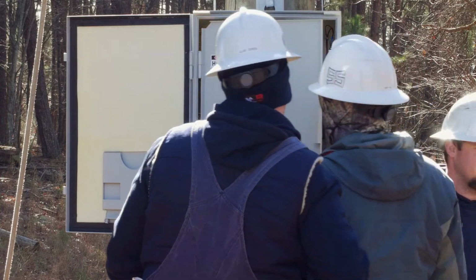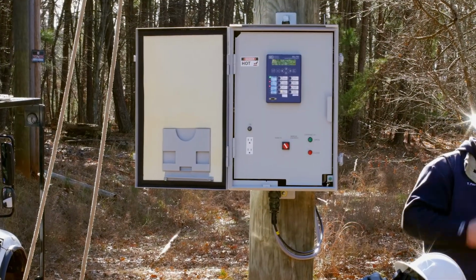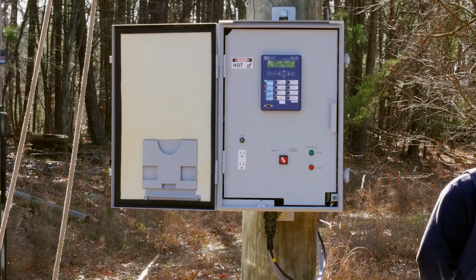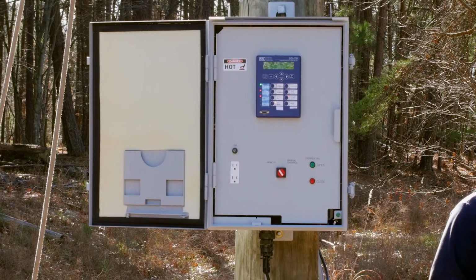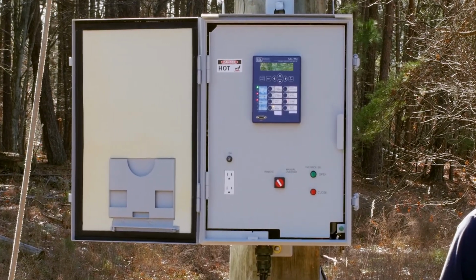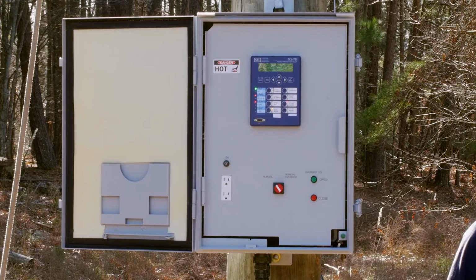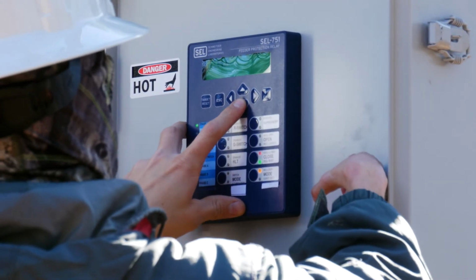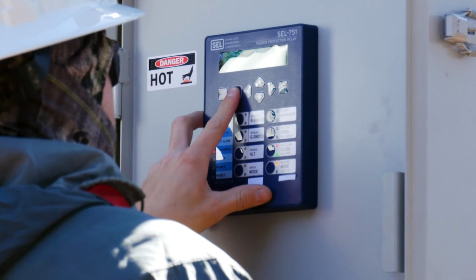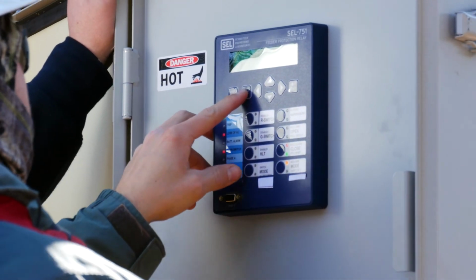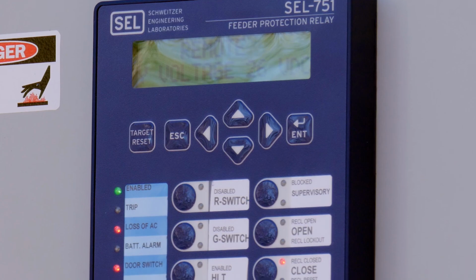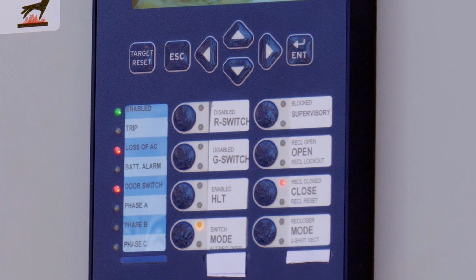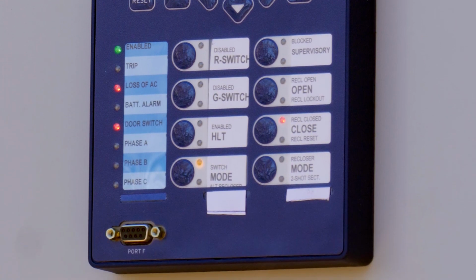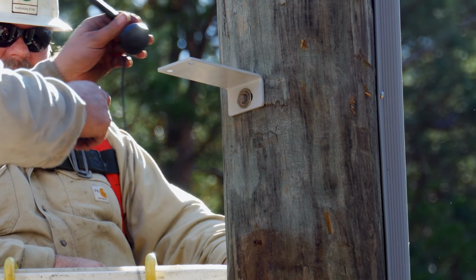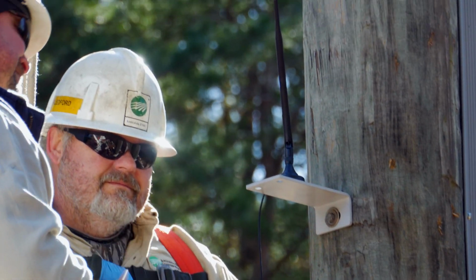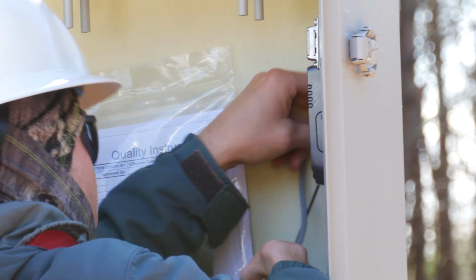Southern States devices will arrive on site with the relay pre-programmed and tested to the device, but the communications and protection settings will need to be added to the relay. Some utilities will program these settings prior to installation, while others will wait until on-site. Whichever method is chosen, programming of the relay is a simple process with communication ports on the front of the device.